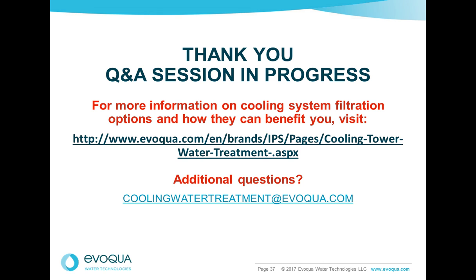Think about it. You're collecting 1 or 2% of your total flow, and you're still pulling in all kinds of dust. It's probably not going to have much of an impact at all. 3% is really the bottom end to have any kind of an impact from a filtration standpoint, up to 5%.